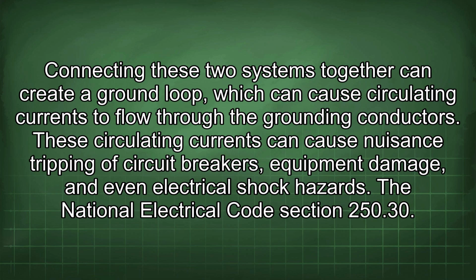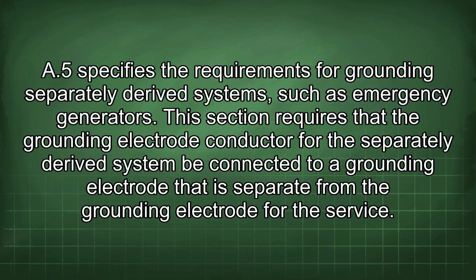The National Electrical Code Section 250.30(A)(5) specifies the requirements for grounding separately derived systems, such as emergency generators. This section requires that the grounding electrode conductor for the separately derived system be connected to a grounding electrode that is separate from the grounding electrode for the service.